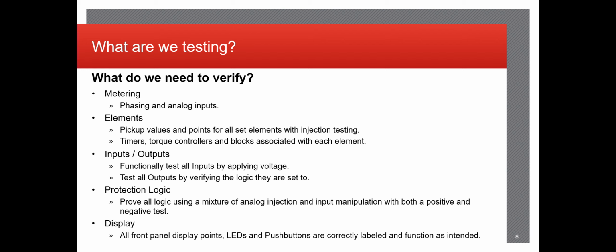The inputs and outputs you test as a relay tech, you're testing within the relay to make sure the relay correctly operates based on the surrounding isolated equipment, such as the knife blades and any lockouts or switches that may be in the scheme. These inputs and outputs also get tested by the testing commissioning engineers functionally, not necessarily by triggering the inputs and outputs based on the relay logic, but more so just to see that the circuit is made up correctly. And speaking on that, the protection logic, you test it to prove all logic using a mixture of analog injection and input manipulation with both the positive and negative tests.